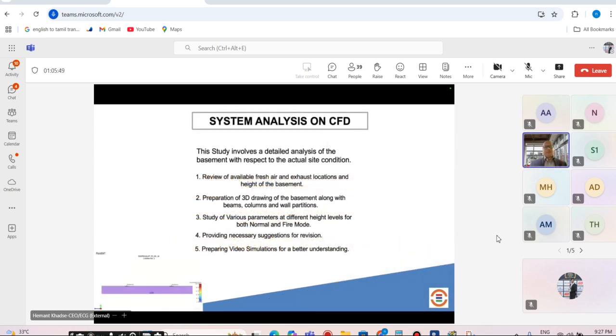CFD is a very important tool nowadays. I'm sure in your country it's a very common practice, but it's going to be the main ingredient of your design to validate your ventilation systems, whether it is effective. So there is a simulation that can be done to validate your ventilation systems, the CFM, the airflow, so that the system that you have installed or you want to install is effective and also has a performance validation using the tool that is available.